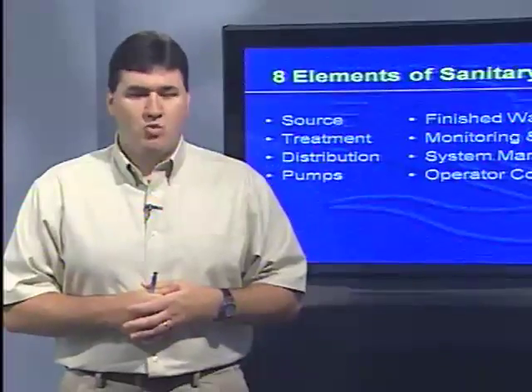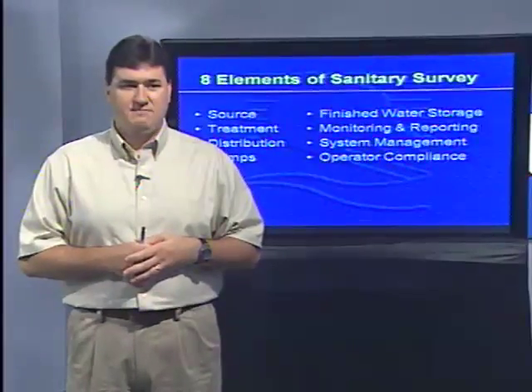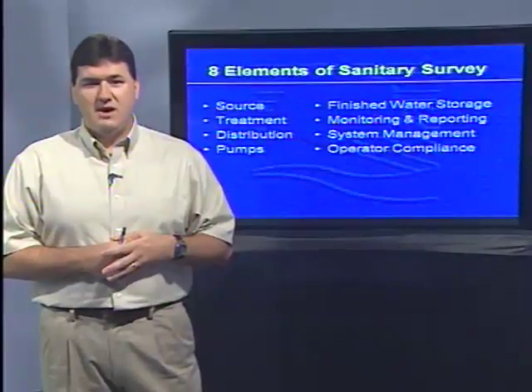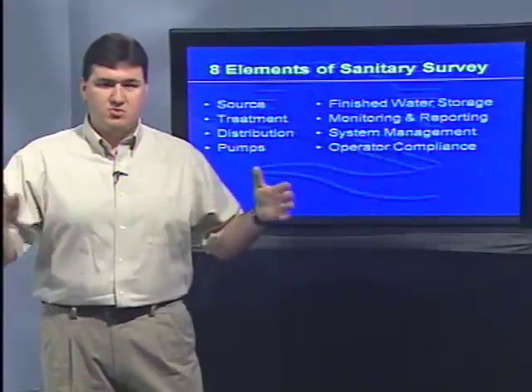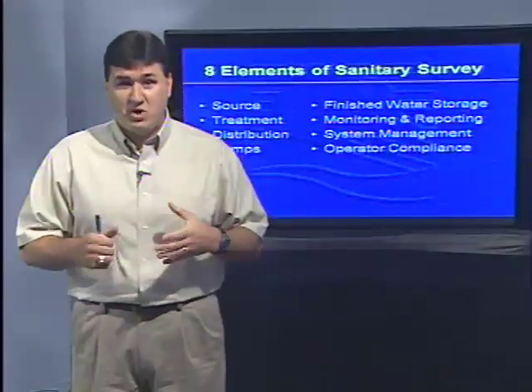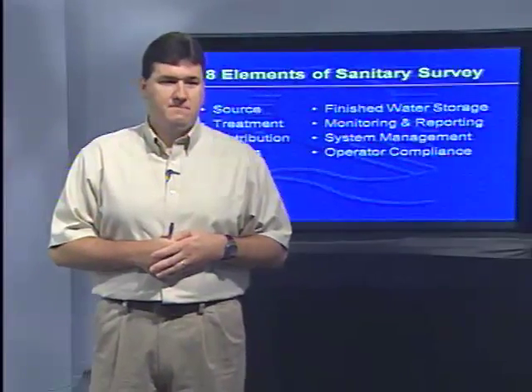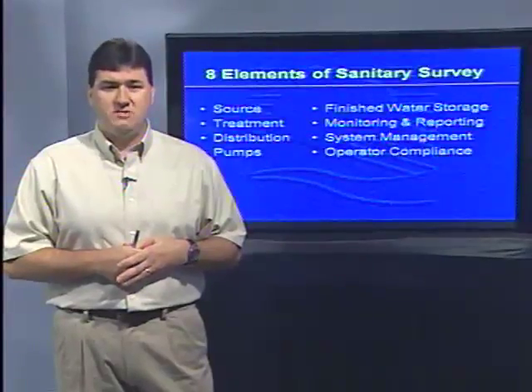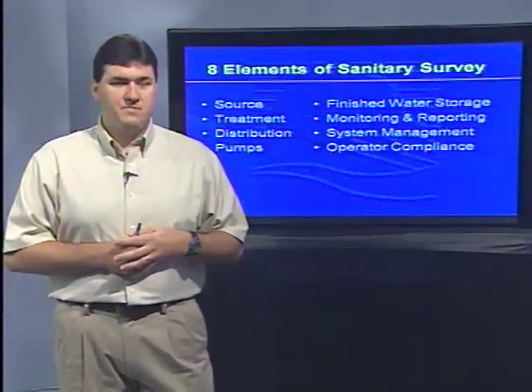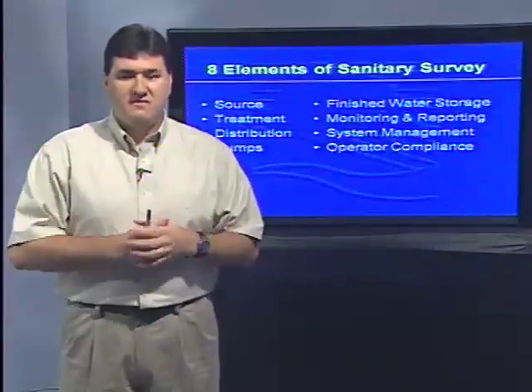The eight elements of a sanitary survey are the same elements we've been using historically. The first is source — we're going to look at your well, the sealing block, well casing, screening vent, and nearby receptors to ensure there are no potential sources of contamination. We'll look at your treatment process — whether simple chlorine injection or a more sophisticated process. We'll evaluate your distribution system, taking pressure readings and looking for leaks. We'll look at your pumps for leaks and adequate capacity.